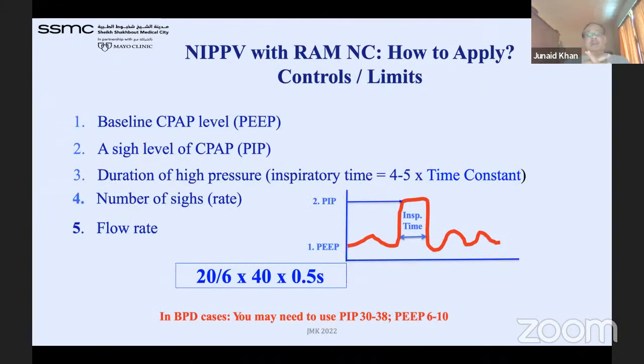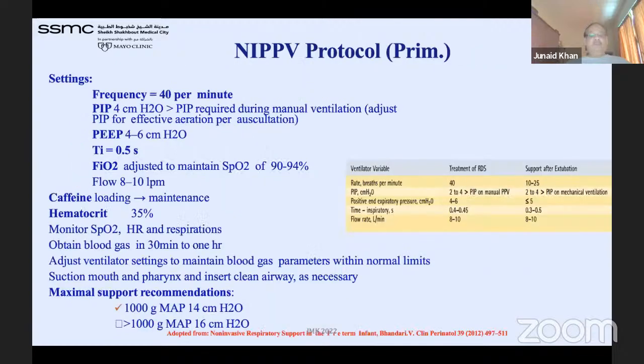Come to the settings. This is a similar, very simple way. The baseline CPAP, which is 5, we put most of the time, or sometimes 6. Then PIP 20, and depending upon how sick the baby is, you can increase up to 25. Duration of the high pressure, inspiratory time, is 4 to 5 time constants, which is 0.5 second inspiratory time, and the rate is about 40. So this is the NIPPV protocol.